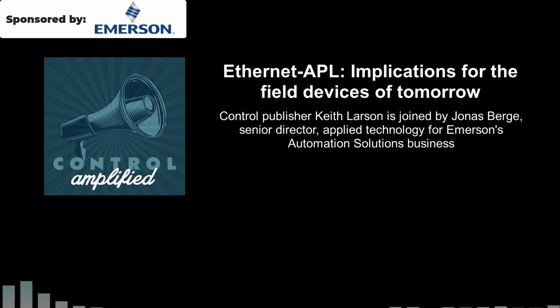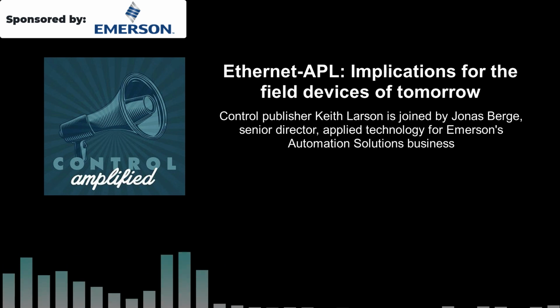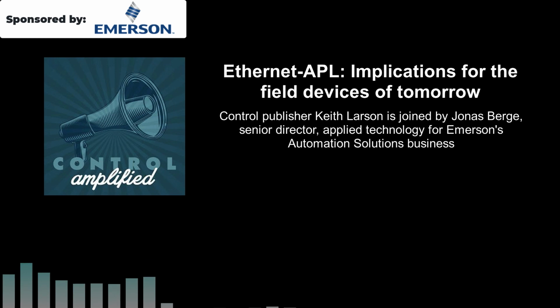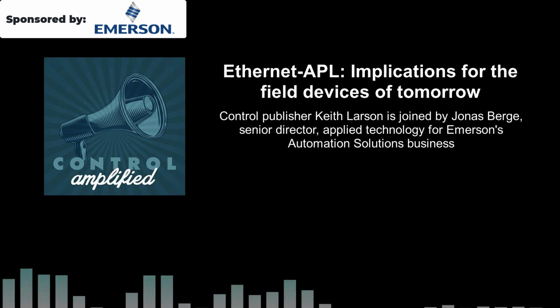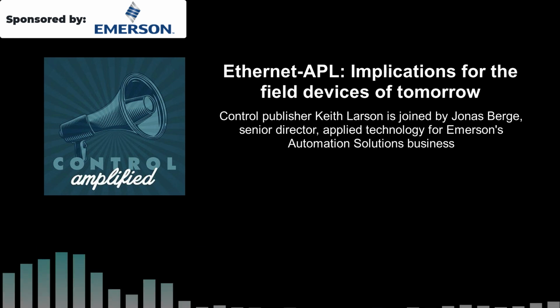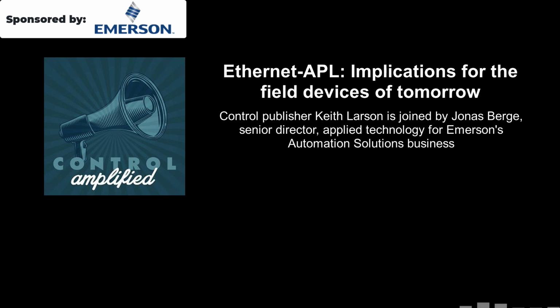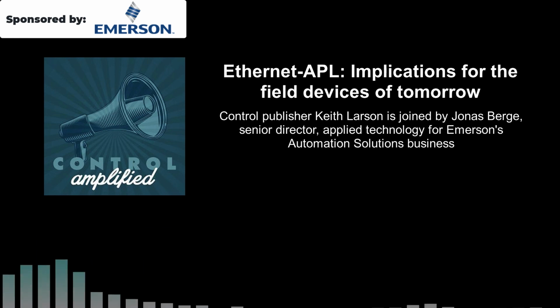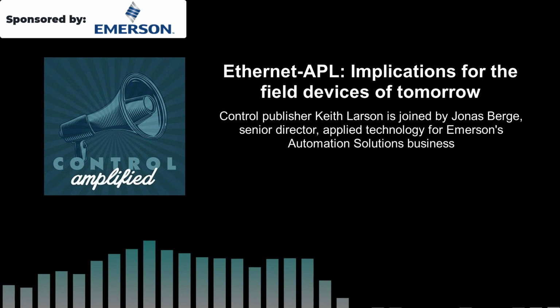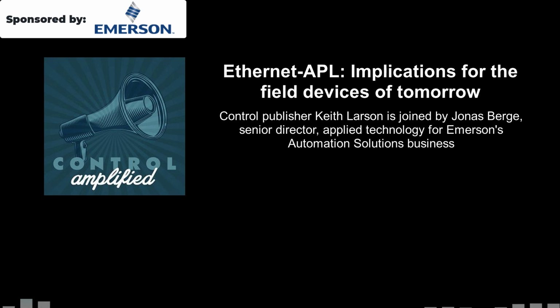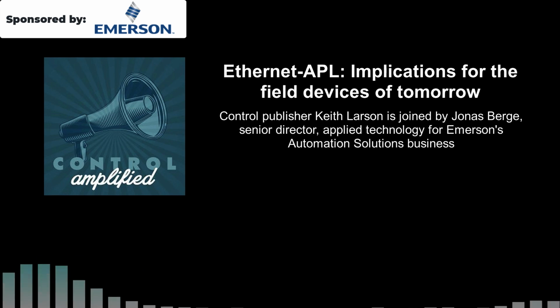That can also be on board the device. So those are perhaps the two biggest points—we learned a lot from Fieldbus and made APL better in this sense. Instruments on Ethernet-APL really hold the promise of a higher level of self-configuration, like we take for granted now with a printer at home or in the office. Instruments will be a lot more like that, with a layer of self-recognition, so you don't have to dig out the CD-ROM with the device driver. You really see that happening in the instrument realm as well.